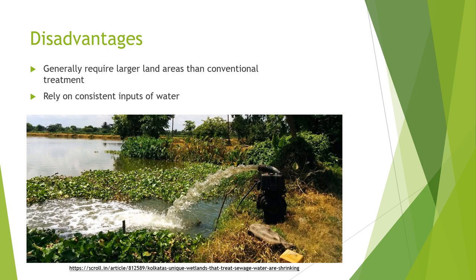While the average performance over the year may be acceptable, wetland treatment cannot be relied upon if effluent quality must meet stringent discharge standards at all times. Additionally, constructed wetlands, just like natural wetlands, require a minimum amount of water to survive. While wetlands can tolerate temporary drawdowns, they cannot withstand complete drying. With this dependence on consistent hydrologic inputs, the effectiveness of constructed wetlands will be negatively affected in arid climates or climates with large seasonal variations in precipitation patterns. However, if there is a way to store sufficient amounts of water nearby, the constructed wetland can receive artificial hydrologic inputs to sustain wetland health and treatment effectiveness throughout the year.